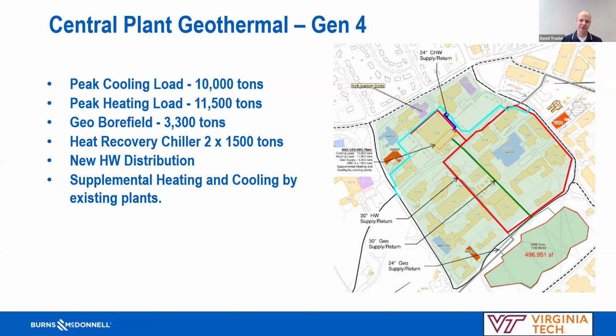So the plan for this part of campus is a new hot water distribution loop connecting to the existing steam-heated buildings, with supplemental heating and cooling from existing plants as needed, since peak loads are 10,000 to 11,500 tons and we're only providing about 3,000 tons. But I think you'll be surprised at the modeling results from this.